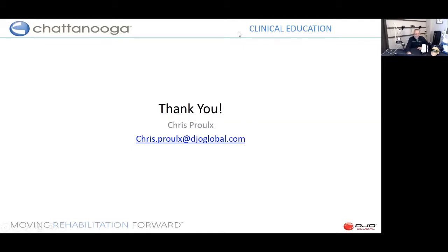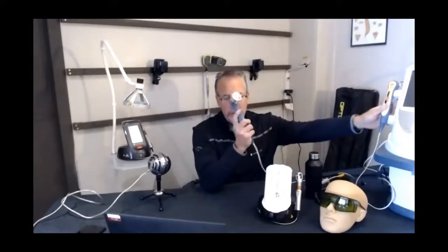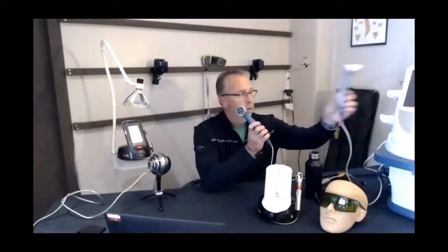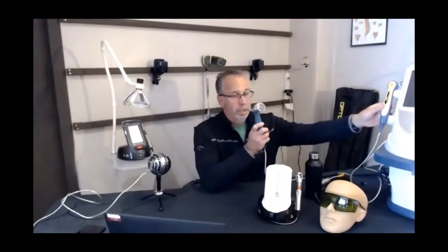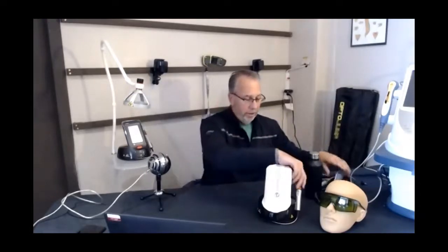I'm going to stop sharing that because I think there was some posting on the chat here. So let me go to the video here. Let me show you. So this is a class 3B laser. I hope you can see my video. There's multiple diodes to it, right? And the silver ones you see are actually the laser diodes. There's different configurations of diodes, depending on your device. So this attaches to this. And here's a single diode laser. This is a gallium aluminum arsenide, and it uses a diode output. The energy production is going to be released from the laser diode here versus this guy here.